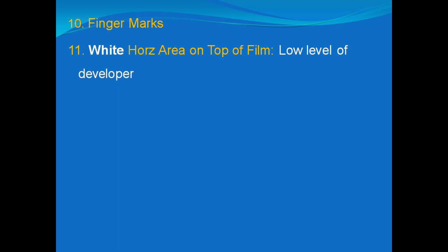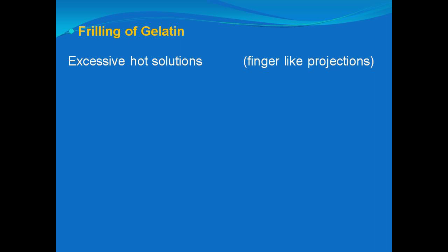The problem of a white horizontal area on top of the film results when the level of developer is less in the developer tank. To avoid this problem, the developer tank should be filled properly so as to dip the film entirely.